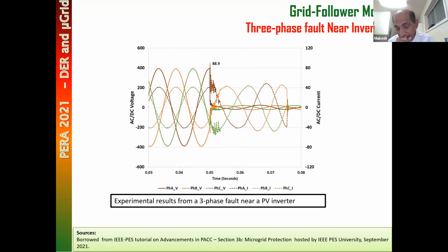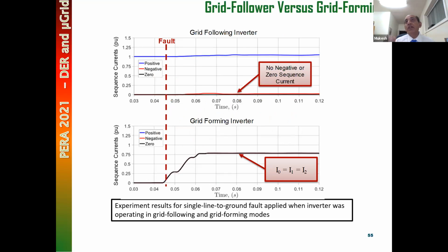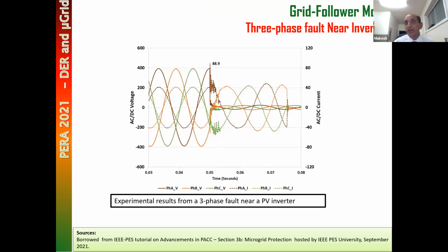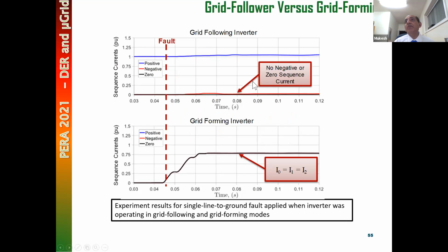Number one point: the battery or inverter source short circuit current is unlike a regular conventional source. With a conventional source, the current goes up. Here the current is almost the same, at least in the same order, for an inverter source. Now look at this. When it's operating in grid follower mode, let's say you apply a line to ground fault. These are experimental results of the same thing. So this was a balanced fault. Now let's look at an unbalanced fault.